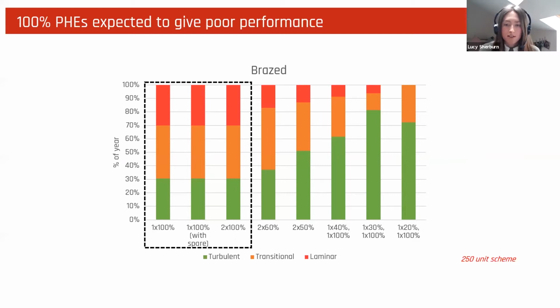Then looking more into brazed plate heat exchangers, I compared the flow regime of different scenarios. As you can see on the graph here, we had one plate sized at 100% of peak load, so your duty scenario. We had the same again, but with a spare plate located in the plant room. This was looking at the cost of that, really. We then had duty standby. We then looked at duty assist approaches, so 2 plates sized at 60%, 2 plates sized at 50%. We've seen these before in industry. And then we also thought to look at using almost like a jockey plate, so having a plate sized at 20, 30 or 40%, and then having a larger size plate as well. So what can we see from the flow regime with this?